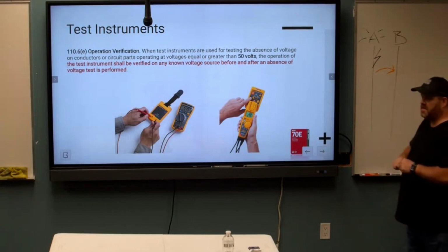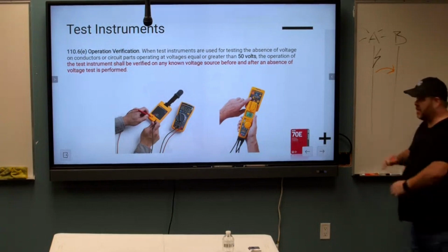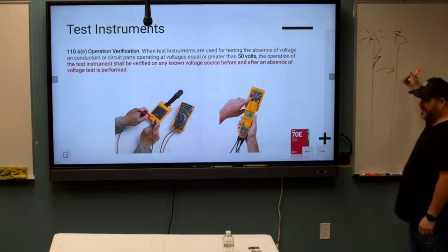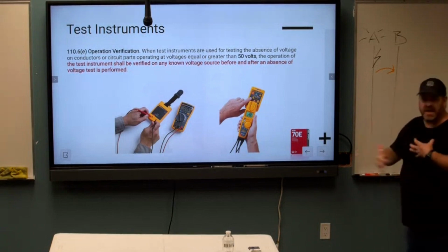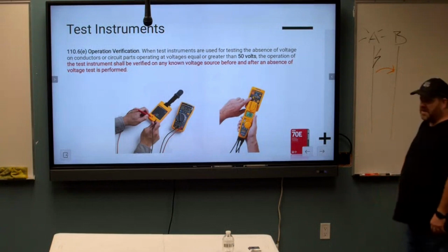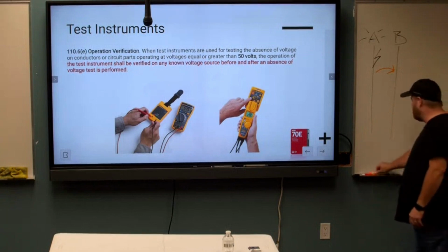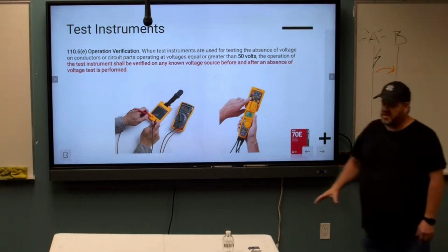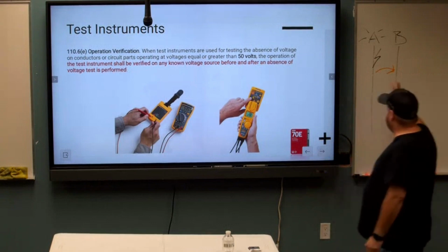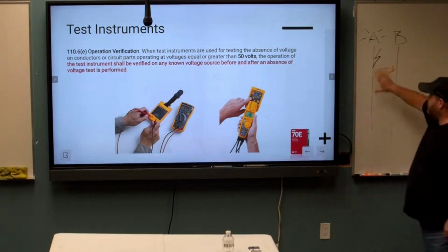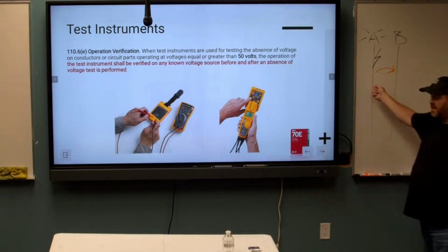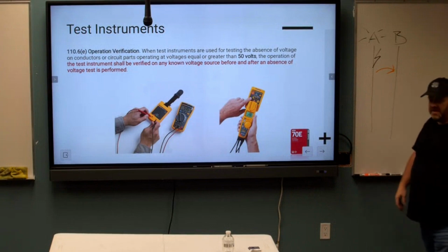Does that make sense? We'd rather have a false positive than a false negative, right? Because that's going to make us more aware. Holy crap, this shouldn't be live. You should be stopping and investigating now. Does that make sense? But the induction testers are really good to use because that'll tell you after you've performed lockout tagout, if that thing lights up, that's a red flag. Maybe you turned off the wrong circuit. You got to investigate. See how that works?